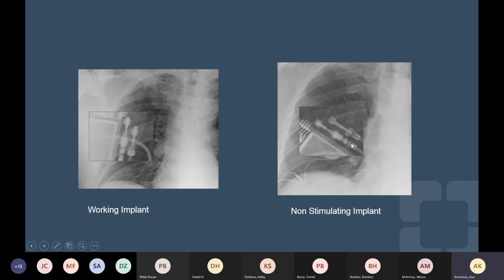And what can happen with the current device is that you can get air pistoning. There's no escape route for the air once it's so tight. Once you put the pin into the pulse generator, it builds up pressure. So now, instead of just our usual original guidance of, stick it in, tighten the little set screw, now you have to have 3 hands doing it. One person holding the device and pushing in and holding in the pin, and then a third hand to tighten the set screw. And I guess that air will eventually siphon out, but it makes it so it's in contact.